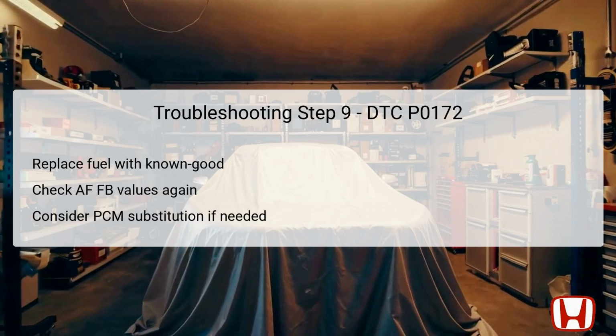For this troubleshooting step, the technician needs to assess the fuel in the tank. It's especially crucial to recognize that if a misfire occurred shortly after refueling, a fuel-related issue is likely. The technician should drain the fuel tank and replace it with known good fuel, ensuring that factors such as unknown additives or impurities are eliminated from the equation.